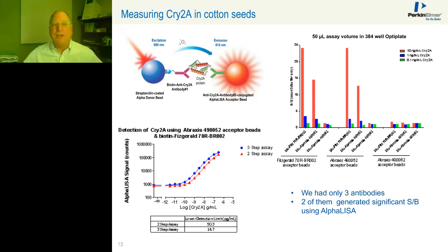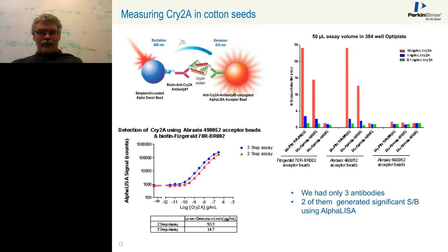And the next question is right back to you, Philippe. The question is, how will you relativize your data once you get beyond the AlphaLISA, and how much background do you get compared to a normal ELISA? So the background issue is actually something you can control. Background is actually extremely low because the chances of two beads crossing each other randomly compared to the volume of an assay well is extremely small. So there's also very little risk of anything sticking to the beads. In some cases, you may have to optimize the assay to guarantee that, but usually it is not really an issue.